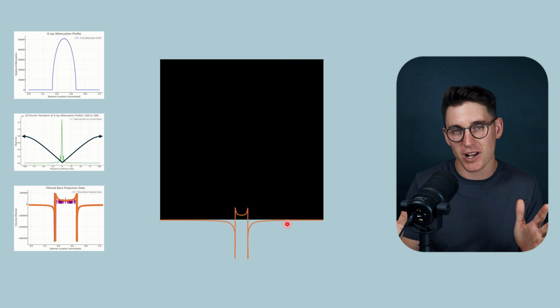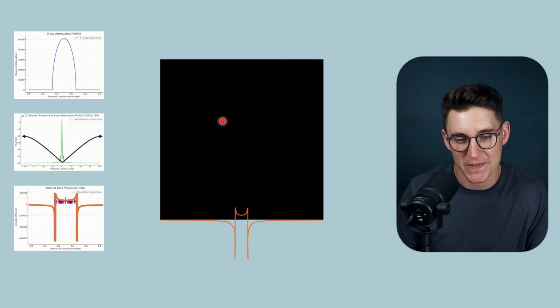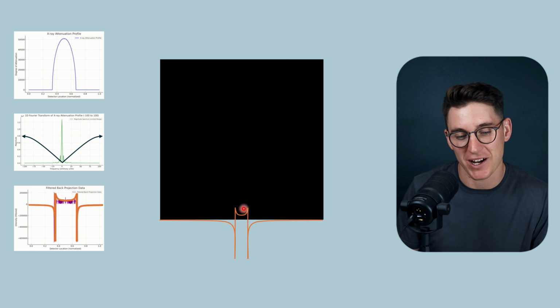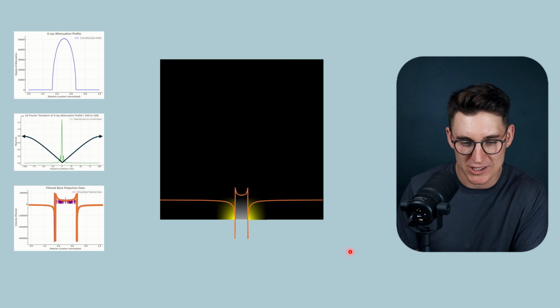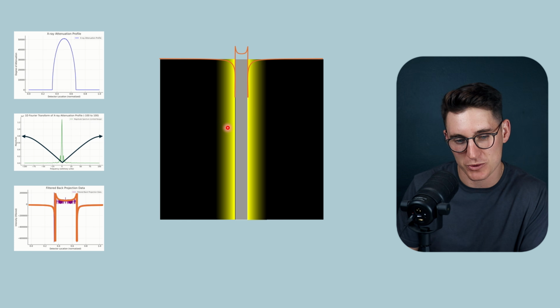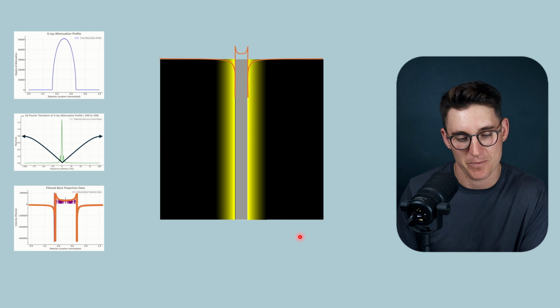We now just apply the process of simple back projection. We smear that data over the angle that the X-rays came from. Positive values are going to be represented by a light color here. Negative values are going to be represented by a yellow color on our image. Notice how as we project that data over, we've created negative lobes on either side of this projection that we've averaged out here. The zeroed part of the image remains 0, remains black. There's 0 attenuation occurring here.